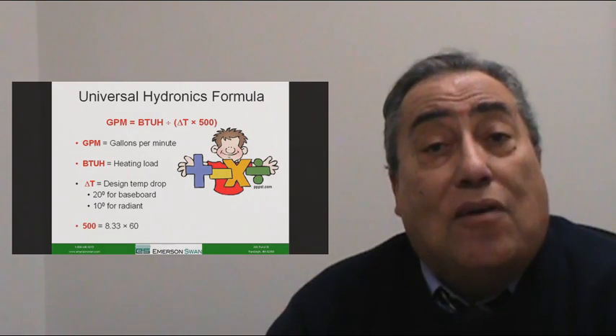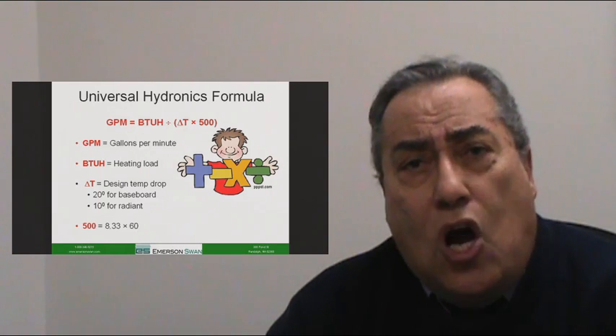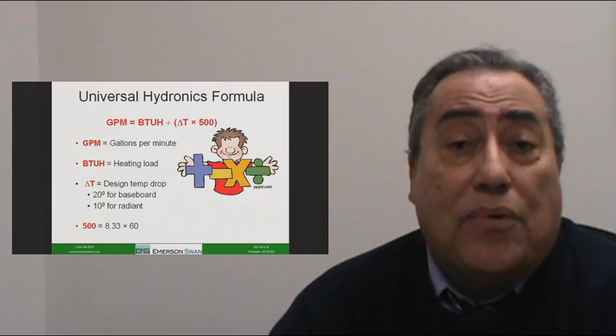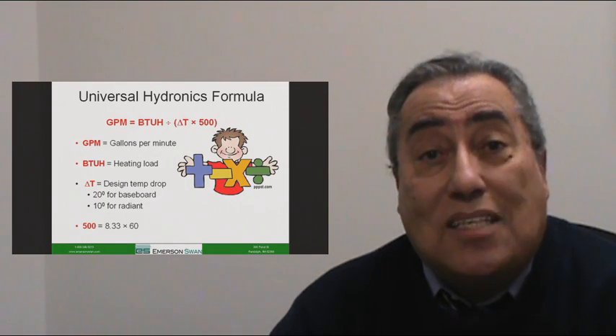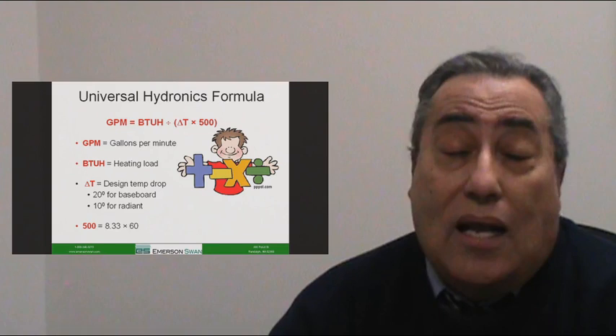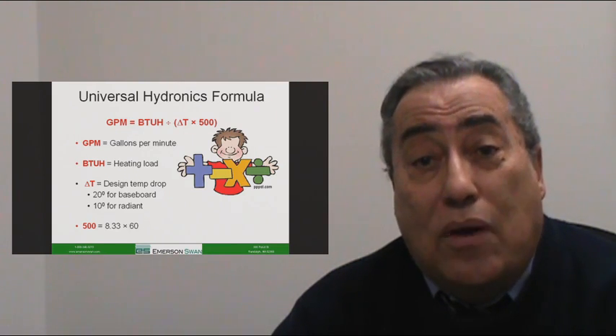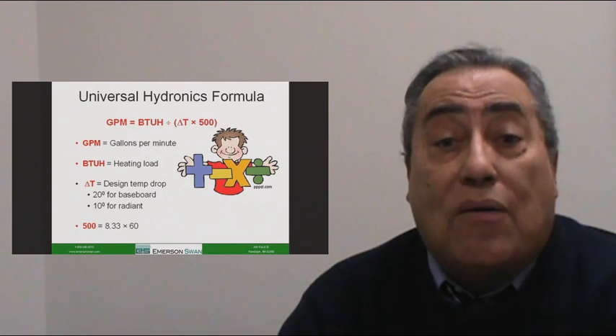Finally, the 500. The 500 is a constant that we use, and it represents 8.33—the weight of a gallon of water—times 60 minutes in the hour. The actual number is 499.8, but we can safely round up to 500.